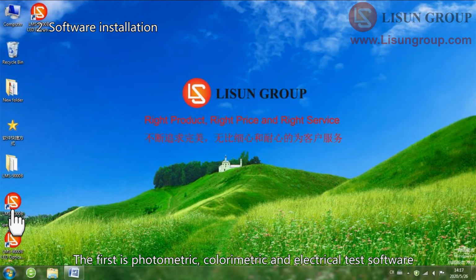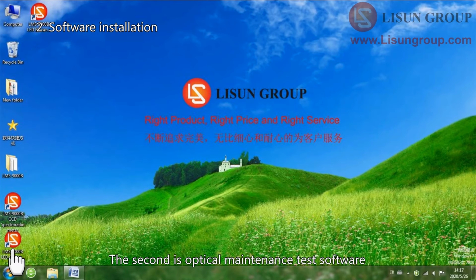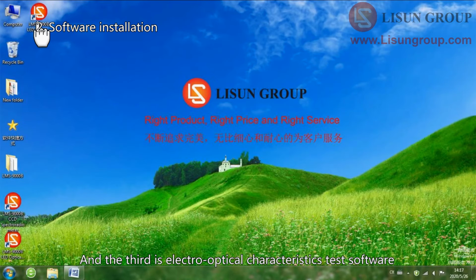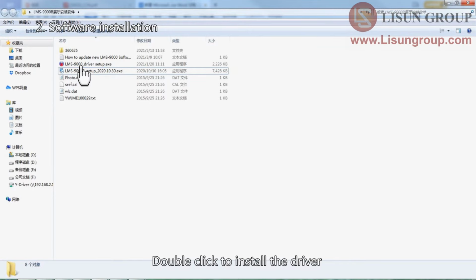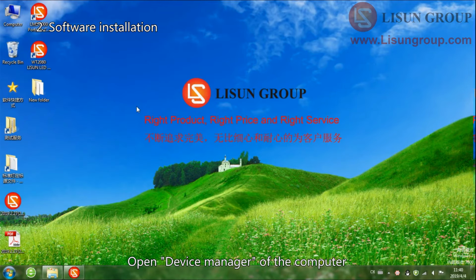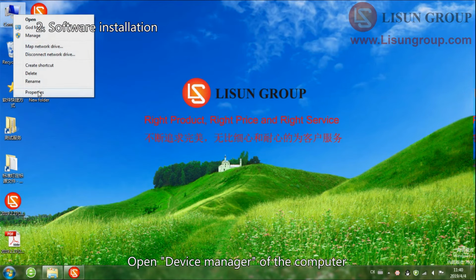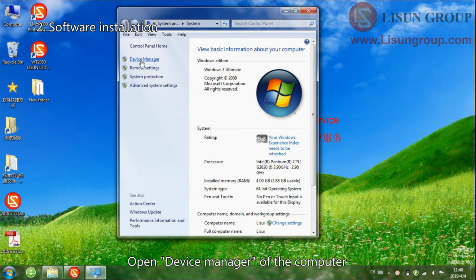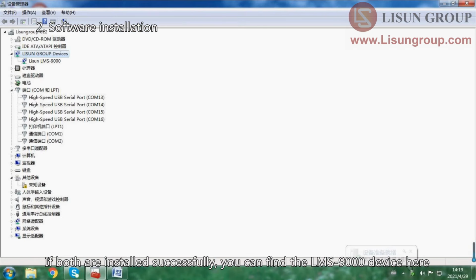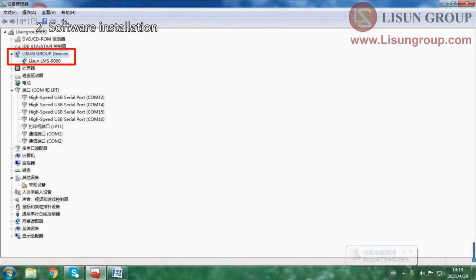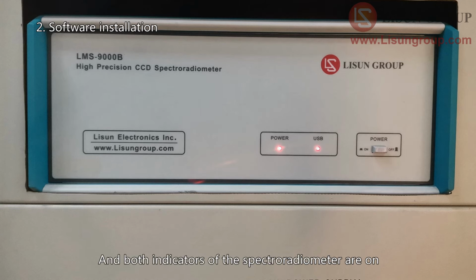The first is Photometric, Colorimetric, and Electrical test software. The second is optical maintenance test software, and the third is Electro-Optical Characteristics Test Software. Double-click to install the driver. Open Device Manager of the computer. If both are installed successfully, you can find the LMS-9000 device here, and both indicators of the spectroradiometer are on.